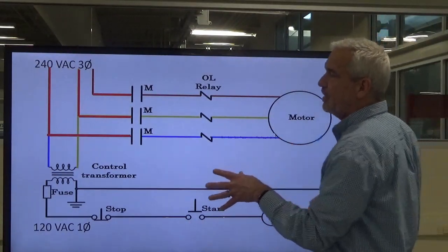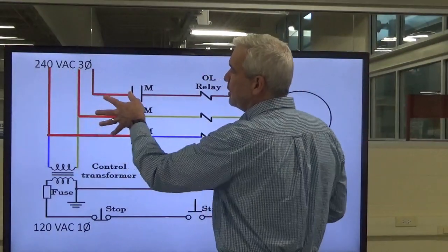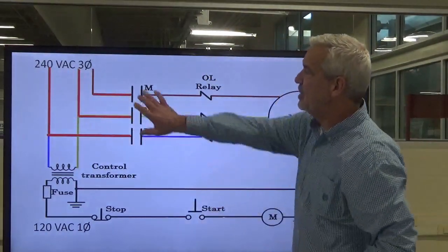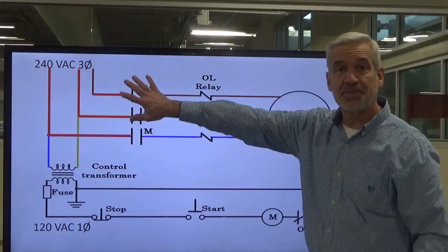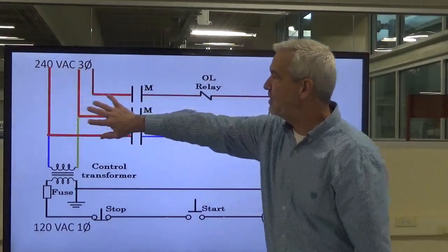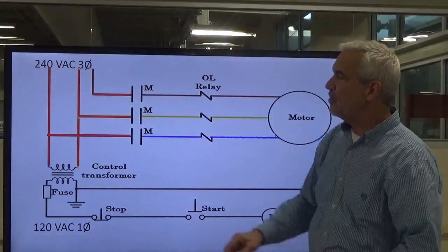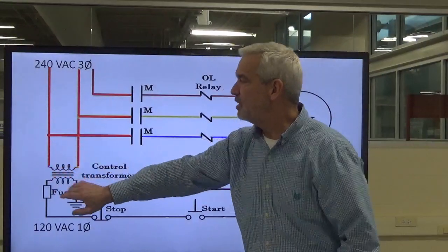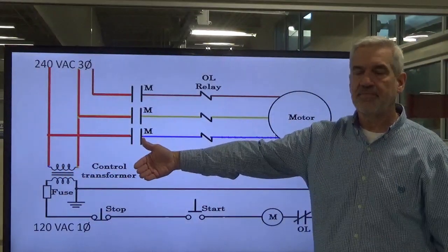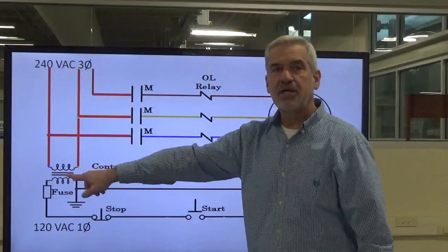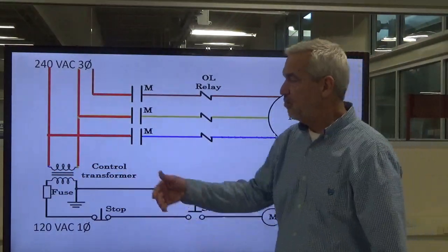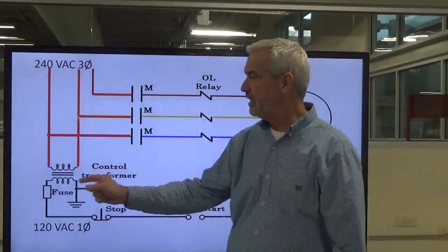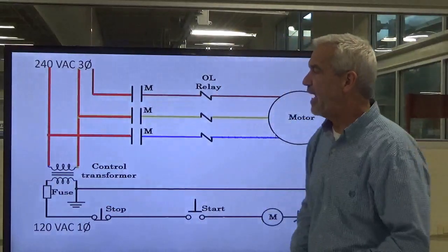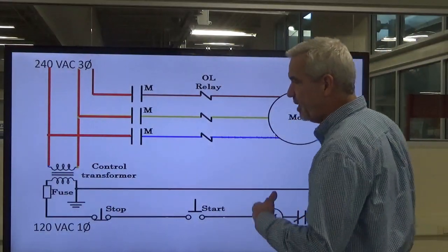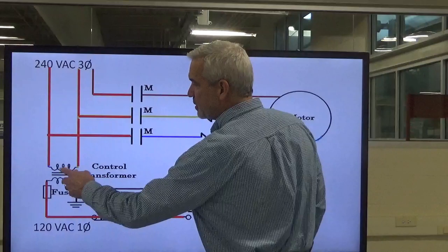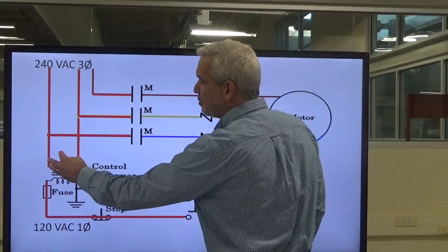So starting off here, we have three-phase voltage going to each of our contacts, just kind of sitting there hanging out. We're not doing anything with it. That's our potential. Okay. So we have our three phases going here, and we also have two of our three phases going to energize the primary coil of our transformer. Okay. And whenever that's energized, we automatically and instantly get voltage coming out of our secondary. Okay. So we've energized our transformer.